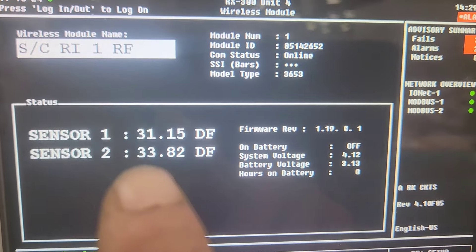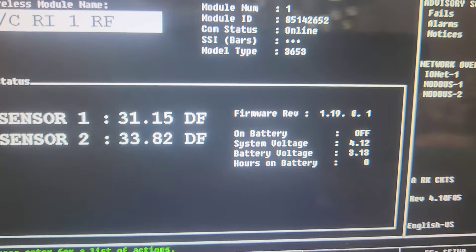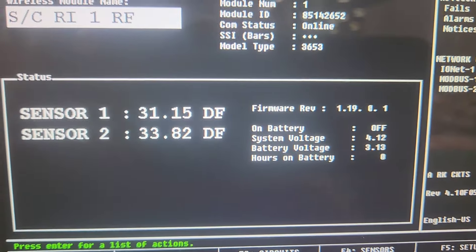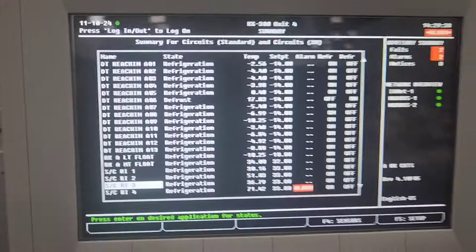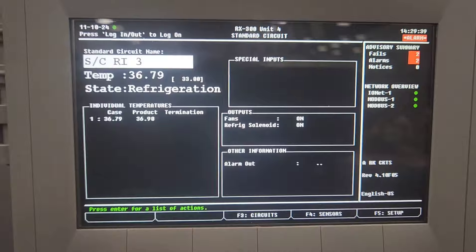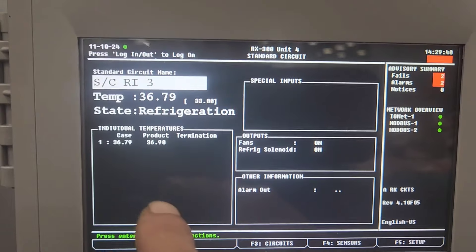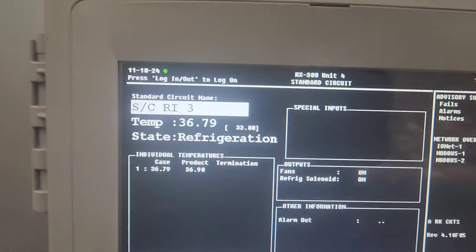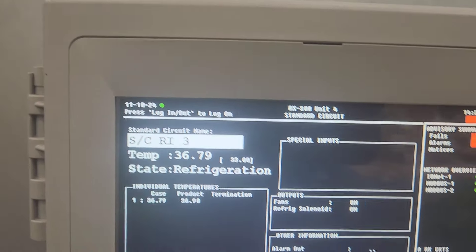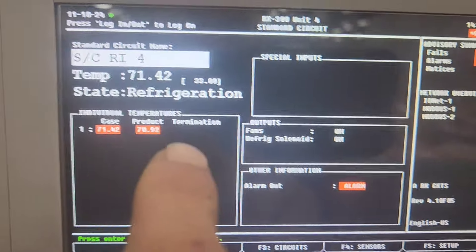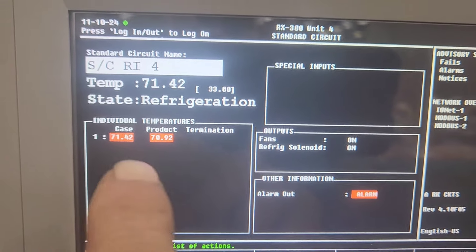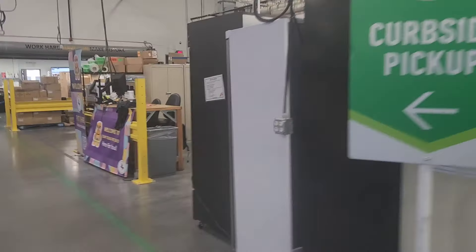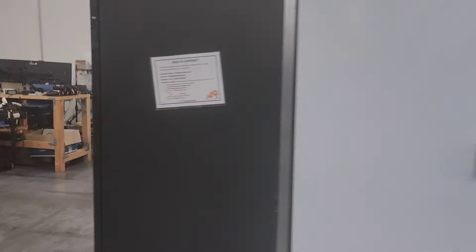You can see both temperatures, the product and the temperature sensor, but at the same time you can go in here and you can see them both right there also. When you go to the one that's alarming, both of them are not like room temperature, so the only one I found was this one.